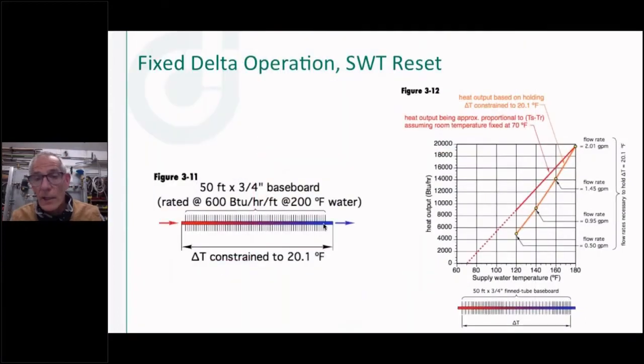All right, so now there's another condition that's going on out there in some of the pumping options that are available today. There's a delta T and a delta P pump. And what the delta T pump does, it tries to keep a set temperature going through the heat emitters all the time. So let's say you designed the system at a 20-degree delta T, the circulator is going to speed up or slow down trying to maintain that temperature all the way from start up to shut off. And basically, if you think about it, it's really kind of like an injection mixing where it's just pulsing that heat in there. It's just trying to match the load by changing the speed of that pump.